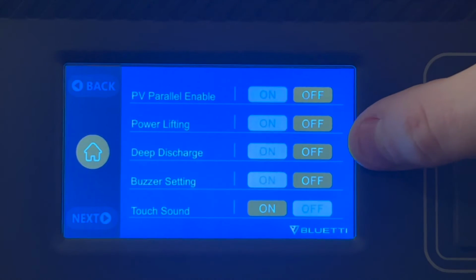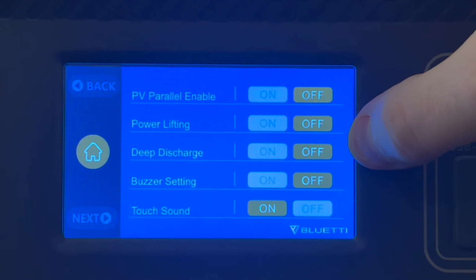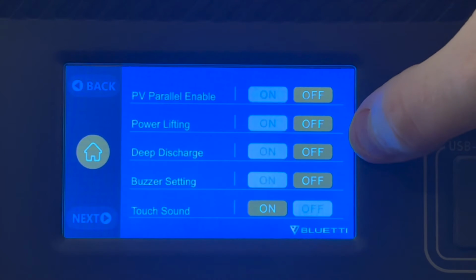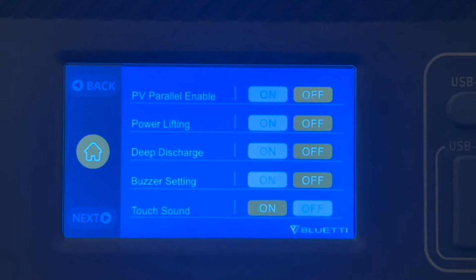If you turn it on, you get that extra 10%, but if you get that battery all the way down to zero, to the point where the BMS will not turn back on, your battery is now toast. There isn't a good way to recover it. So this option is pretty much for emergency use. You're in the middle of a storm, it cuts off, you absolutely have to have this thing on for another couple of hours. Then you can go in there and turn this on. That's what it's for. It will give you the full capacity of the battery, but it is a risk that it could damage the battery when you do that. They even warn you if you go in there to turn it on.